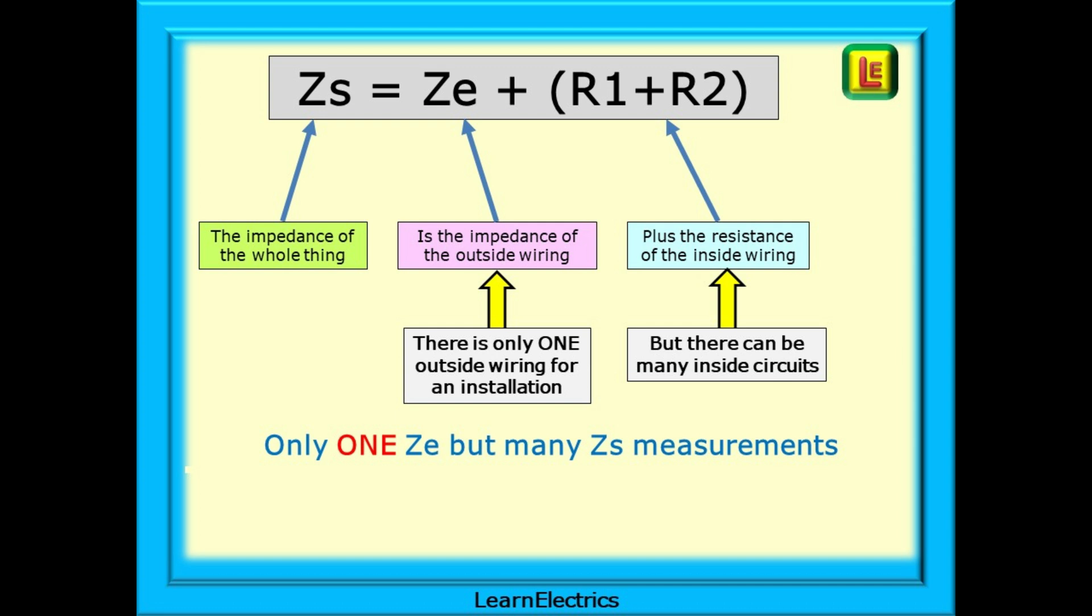Ze is the impedance of the outside wiring and there is only one outside wiring for any installation so there can only be one Ze. All the circuits share the same Ze. R1 plus R2 is the effective resistance of the internal circuit wiring. It's a dead test resistance from the consumer unit to the point of use. Each circuit in the property will have its own R1 plus R2. There can be lots of circuits so there can be lots of R1 plus R2 readings and an equal number of Zs measurements.